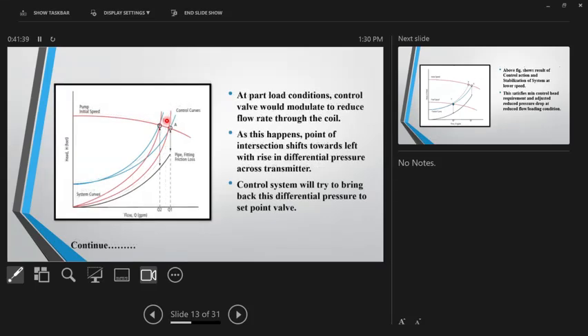It's good. Yeah. Now, how does it happen in real time? Now at part load conditions, we all know that the AHU control valves would try to reduce the flow through the coil. There could be 6-7 AHUs out of 10 that would tune down their two-way valves, and that's how the flow in the overall system would reduce.